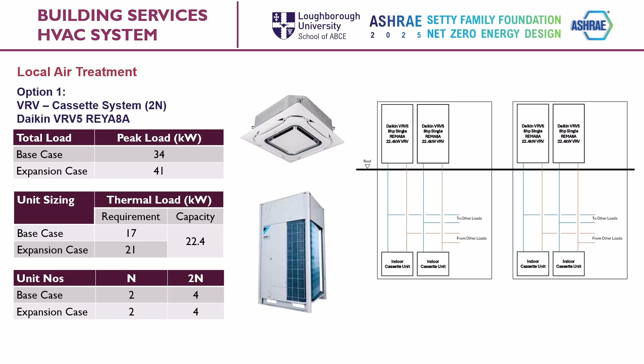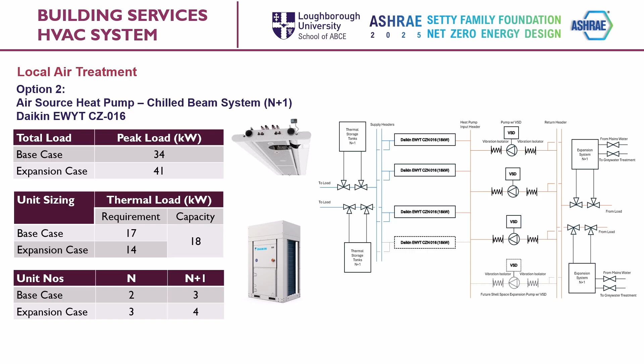The VRV will be sized for a redundancy of 2N, for which the selected VRV unit is the Daikin VRV5 REYA8A, which has a thermal capacity of 22.4 kilowatts each, giving both cases an N equals 2. Similarly, the heat pump system will be sized for a redundancy of N+1. The selected heat pump unit is the Daikin EWYT CZN016, which has a peak thermal capacity of 18 kilowatts each, giving a base case of N equals 2 and an expansion case of N equals 3.